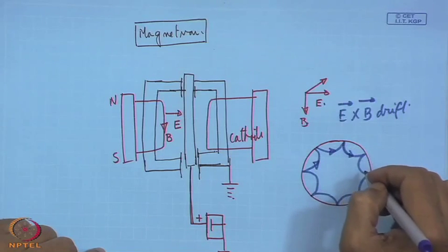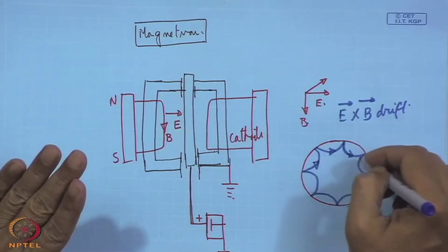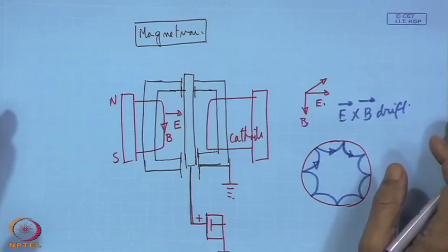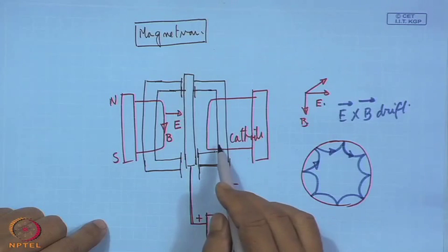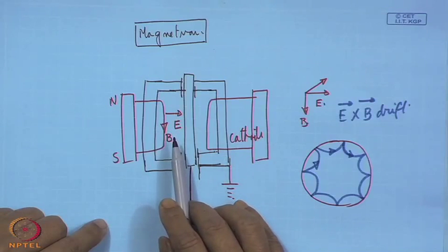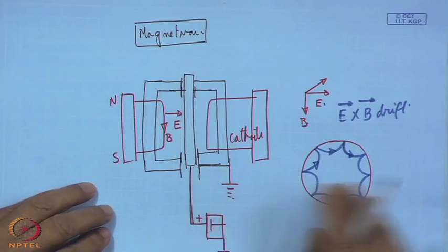That means its path is longer, and these electrons are more efficient in that they have a longer path. In this longer path, an electron has a fair chance of hitting and ionizing a neutral, even at low pressure. This is called an inverted magnetron because here the anode is positively polarized and the cathode is grounded. This inverted magnetron type gauge is also used for very low pressure measurement.